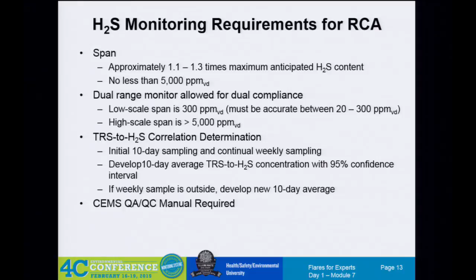If you sample upstream of the water seal, how are you going to get a correlation that sticks every week based on your 10-day event if it's wildly fluctuating? You're pretty much stuck doing your 10-day correlation sampling every day. It's a tough situation, which gets people thinking, why go this route? Save yourself the headache and go with the total sulfur monitor.